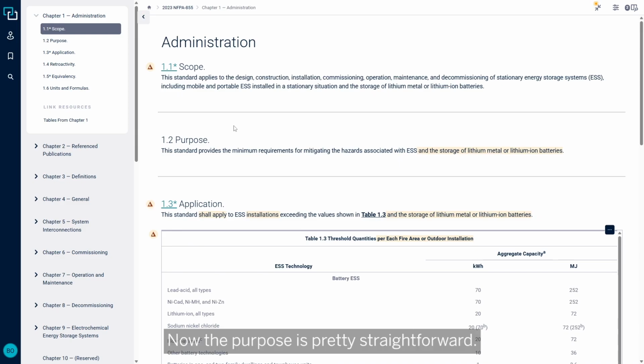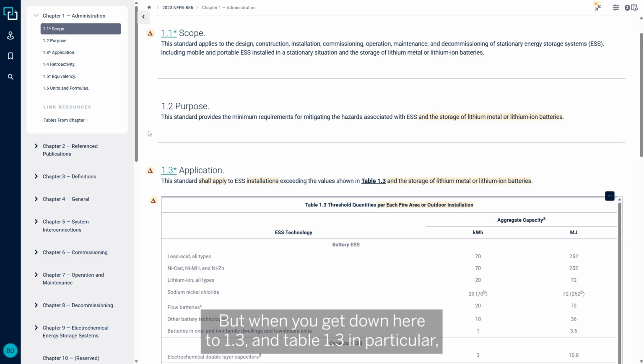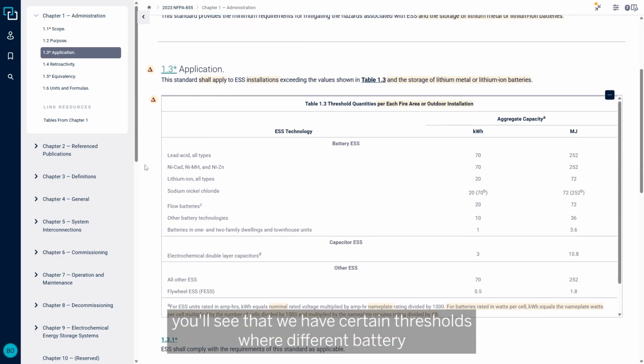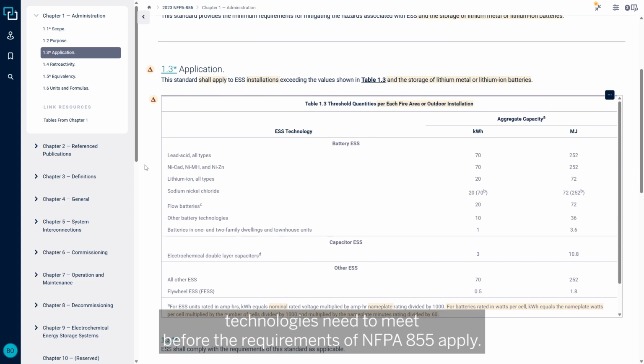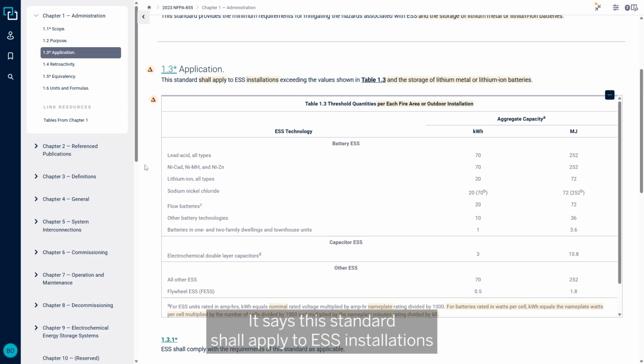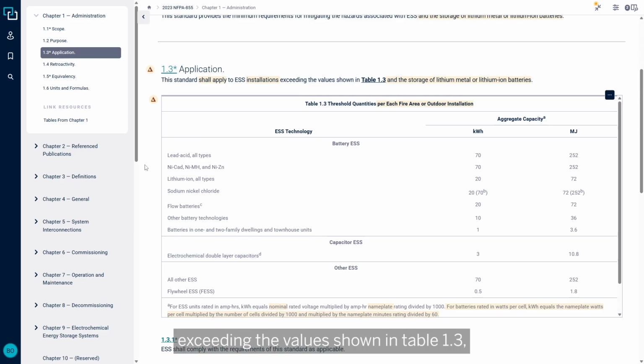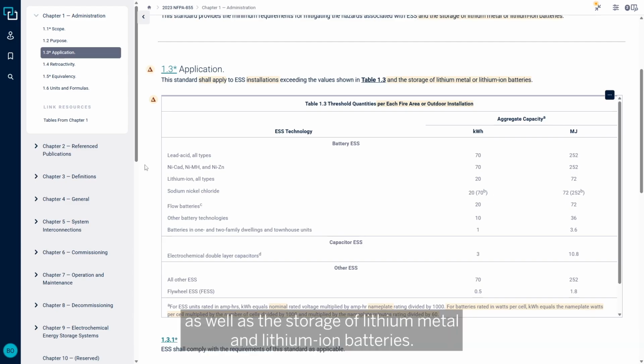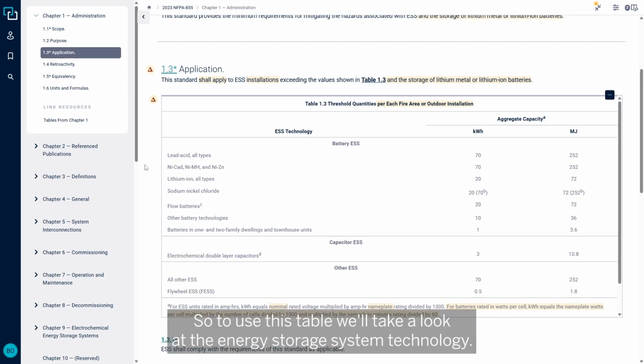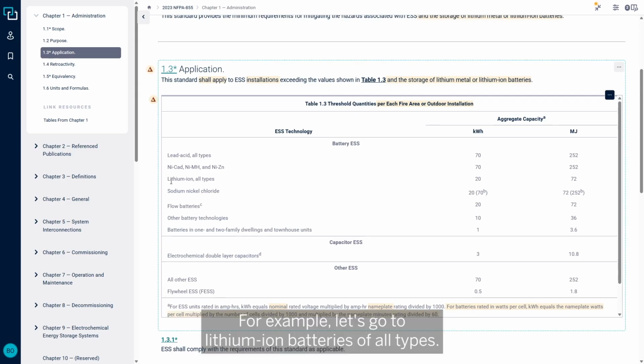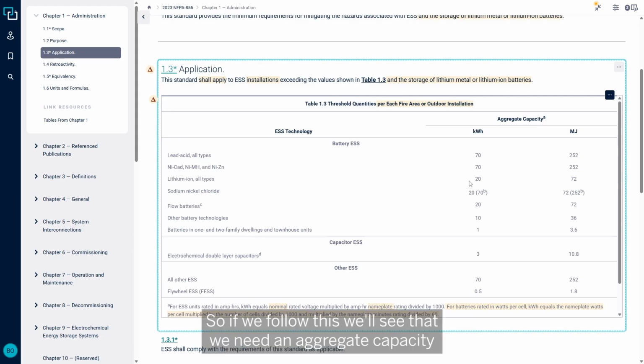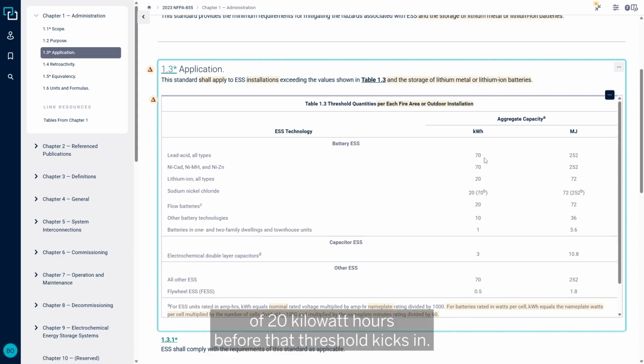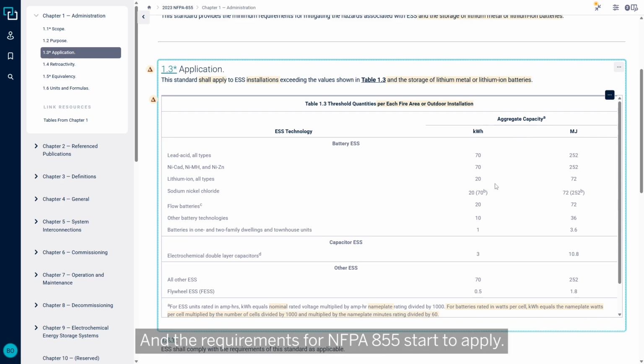Now the purpose is pretty straightforward, but when you get down to 1.3, and Table 1.3 in particular, you'll see that we have certain thresholds different battery technologies need to meet before the requirements of NFPA 855 apply. It says this standard shall apply to ESS installations exceeding the values shown in Table 1.3, as well as the storage of lithium metal and lithium ion batteries. To use this table, we'll take a look at the energy storage system technology. For example, let's go to lithium ion batteries of all types. We'll see that we need an aggregate capacity of 20 kilowatt hours before that threshold kicks in and the requirements of NFPA 855 start to apply.